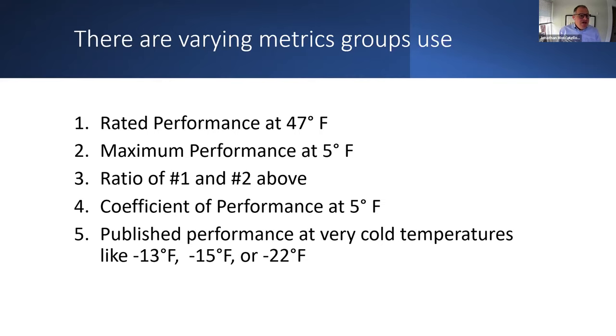There's a ratio of numbers 1 and 2, and this becomes really important to a lot of programs. They want to see this ratio of performance be really high. For Daikin and Mitsubishi, our brand standards are nearly identical. Our brand for cold climate says we will have 100% of the rated capacity still capable and being produced at 5 degrees. And so I think that's a really important number. NEEP and Energy Star have a much lower number. And Sean, I think we're in agreement, right? That we think that 100% is really important and useful.